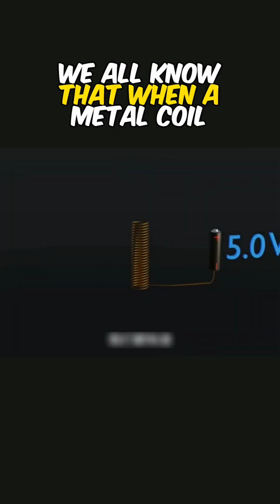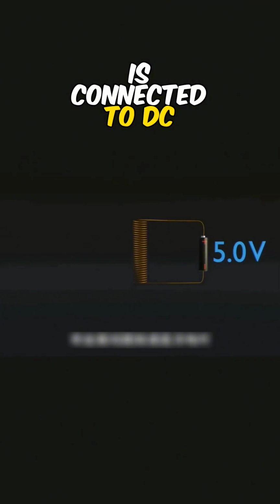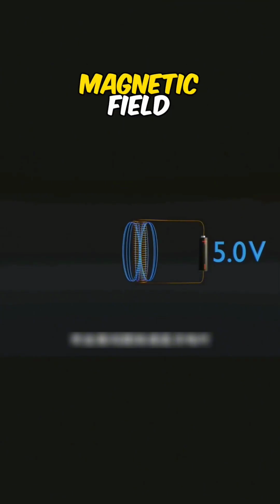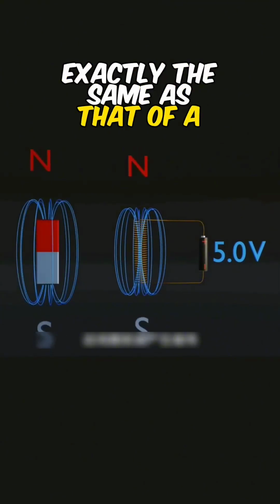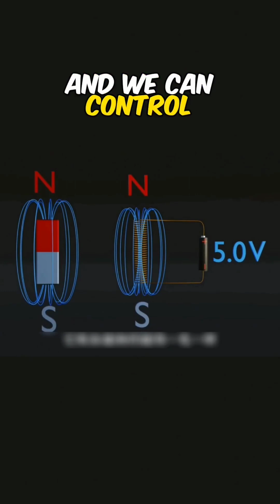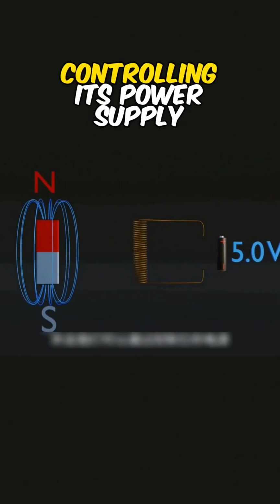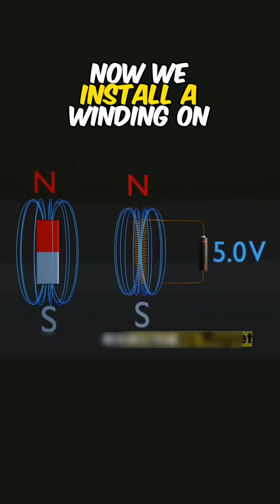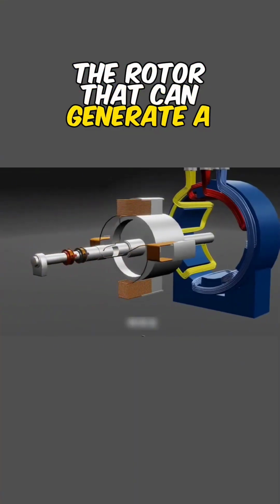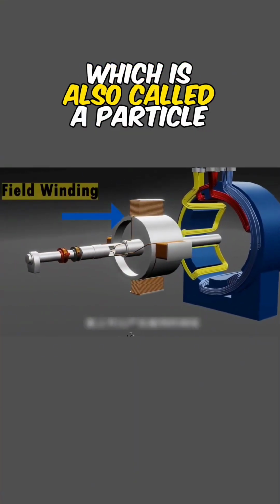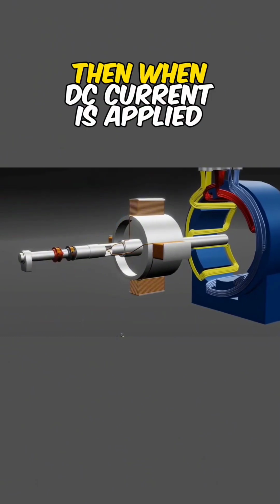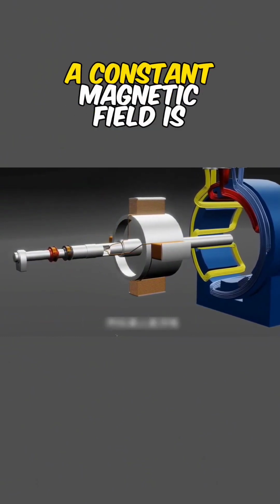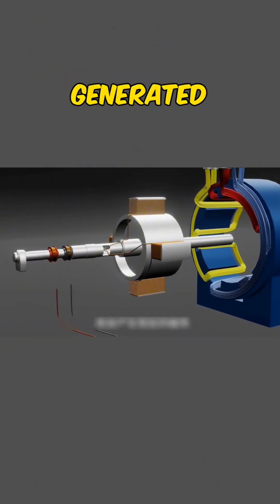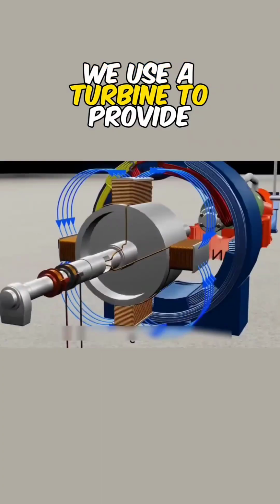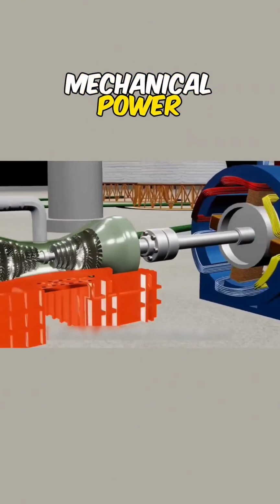We all know that when a metal coil is connected to DC, the coil will generate a magnetic field exactly the same as that of a permanent magnet, and we can control its magnetic field by controlling its power supply. Now we install a winding on the rotor that can generate a magnetic field, which is also called a field winding. Then, when DC current is applied, a constant magnetic field is generated. At this time, we use a turbine to provide mechanical power to the rotor.